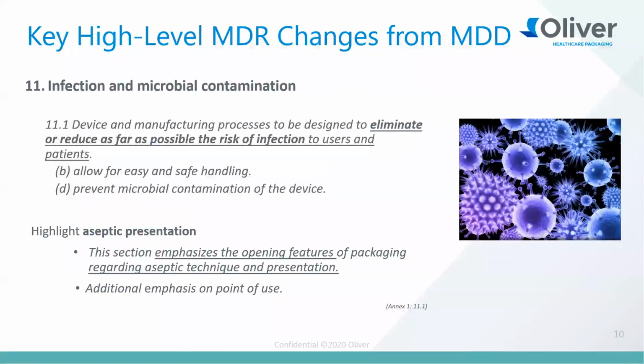Now, focusing on other high-level MDR changes, one is Section 11 on infection and microbial contamination. Section 11.1 says the devices and manufacturer processes shall be designed to eliminate or reduce as far as possible the risk of infection to users and patients. Under this section there are two new concepts, in points B and D: B, to allow for ease and safe handling, and D, to prevent microbial contamination of the device. This emphasizes, at a high level, aseptic presentation, and so emphasizes the opening features of packaging and aseptic technique and presentation.